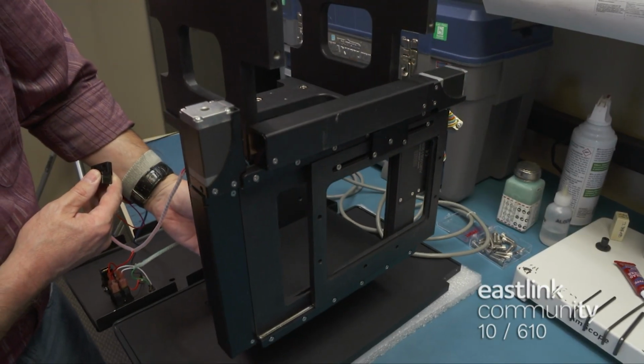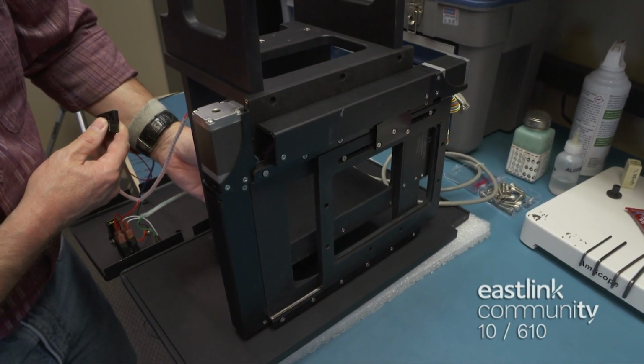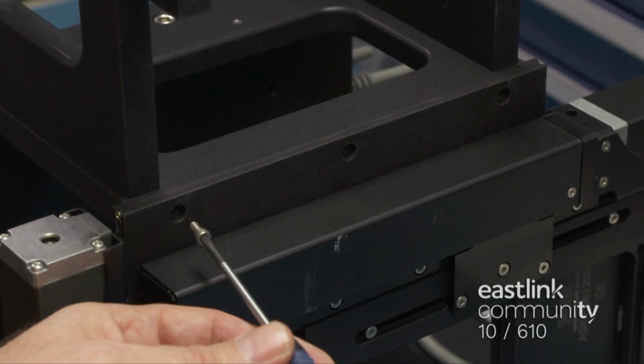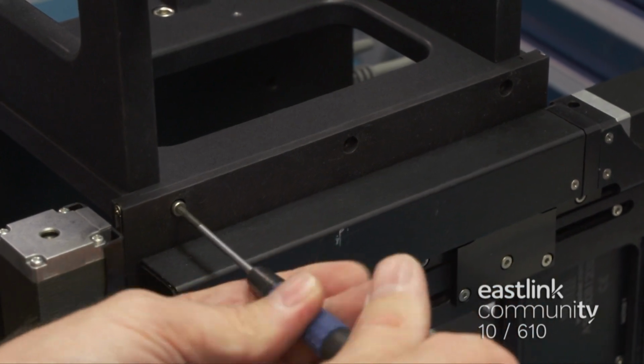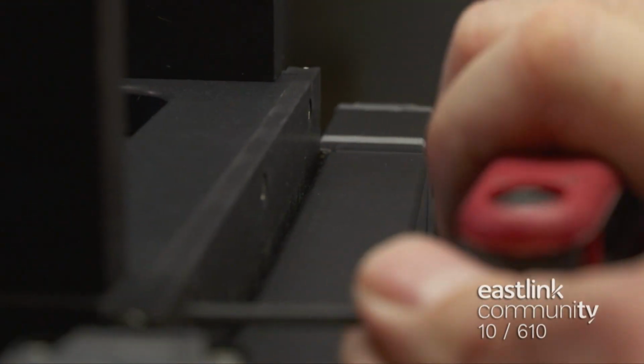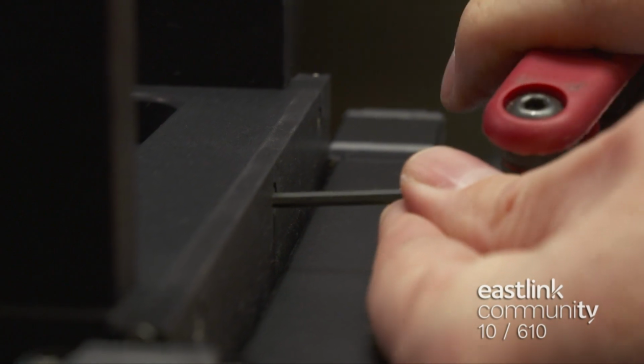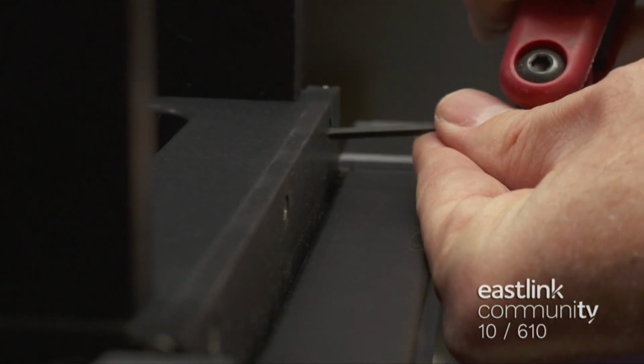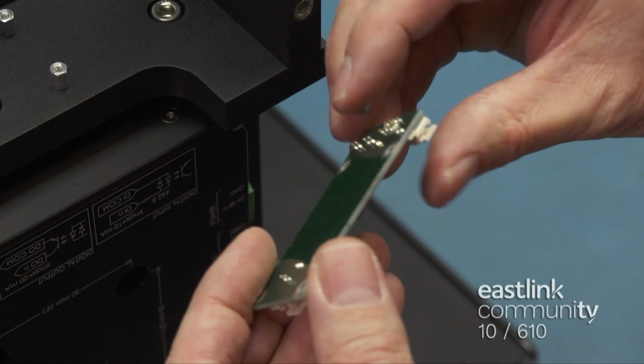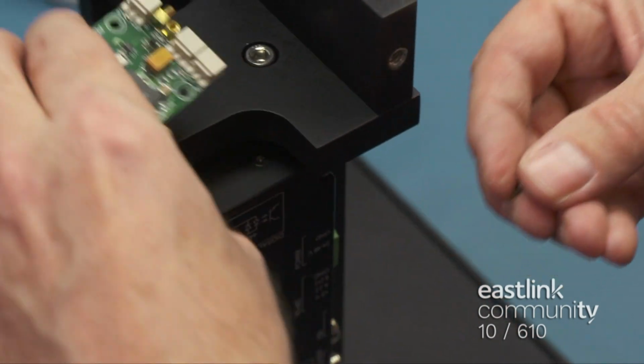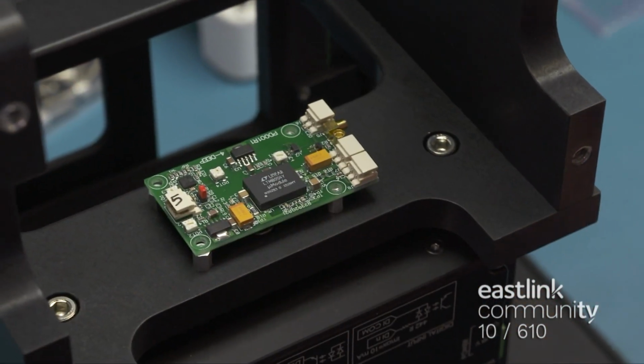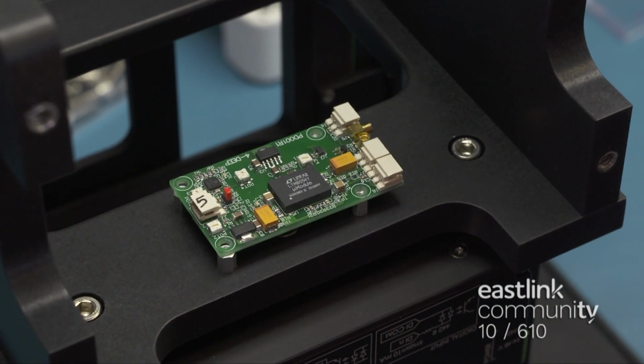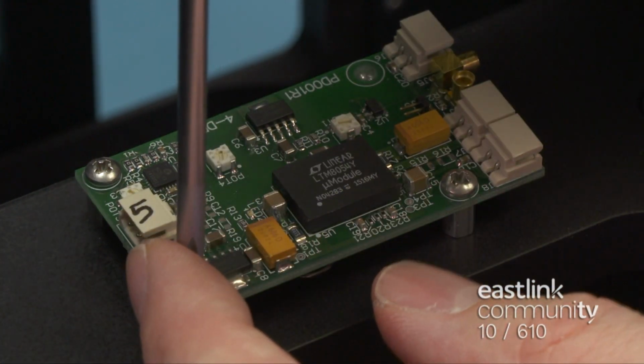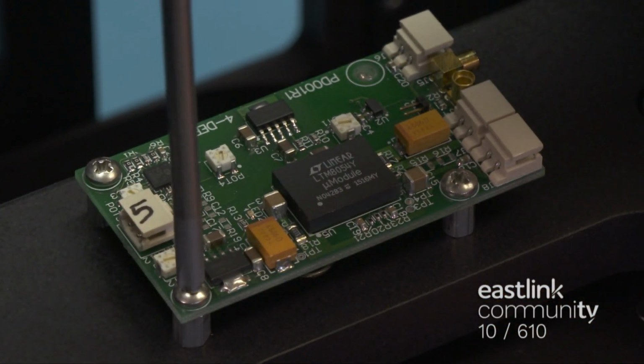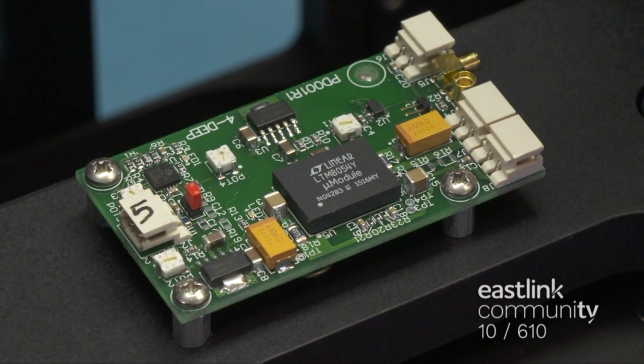The XY aperture stage now has power, and it's moved into position to allow the technologist access for the remaining screws to be installed. The cables are removed to allow for further assembly and will be reattached later. The main circuit board of the filter scan unit is a power driver. It supplies power to both the camera and the laser inside the unit. The power driver also allows the camera to pulse the laser with each frame. It's screwed in place.